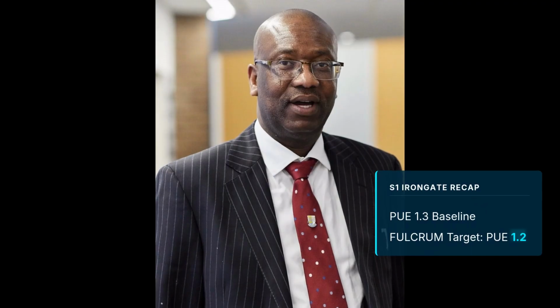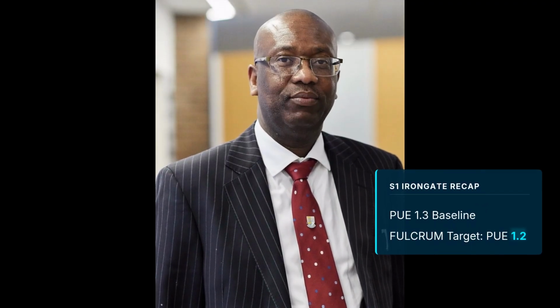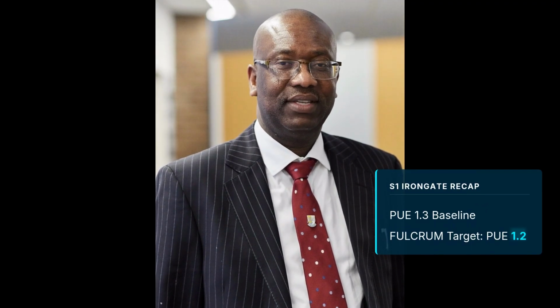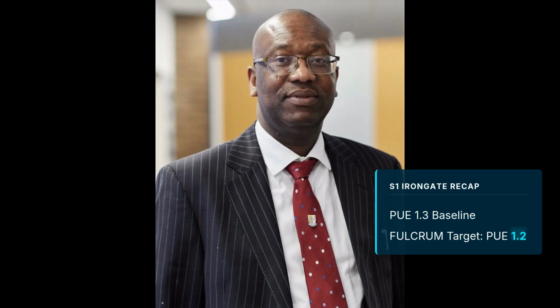In Series 1, Iron Gate achieved a world-class PUE of 1.3 using water-cooled chillers, but at FULCRUM, our target is a mission-critical 1.2. To drop that final point at this massive scale, the strategy must be fundamentally different. We are aiming for zero mechanical chiller energy for more than half of the year. And most importantly, we are redirecting 85 megawatts of waste heat to thousands of local homes. This is hyperscale cooling reimagined for a net zero future.